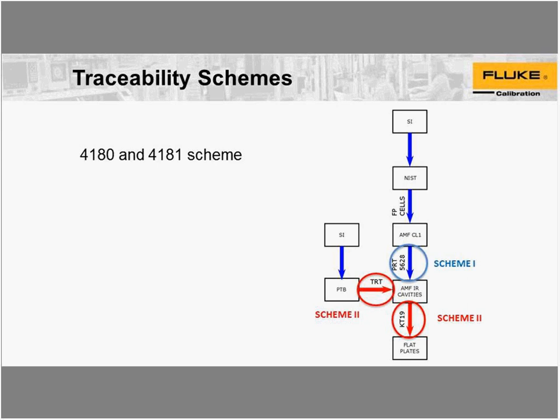What we do to verify our cavities is a verification using Scheme 2 traceability with a traceable radiation thermometer calibrated at PTB — PTB is the NMI in Germany. We use this cross-check using a normalized equivalence type test, similar to what's used in a proficiency test or interlaboratory comparison. That cross-check has traceability to the SI through PTB.